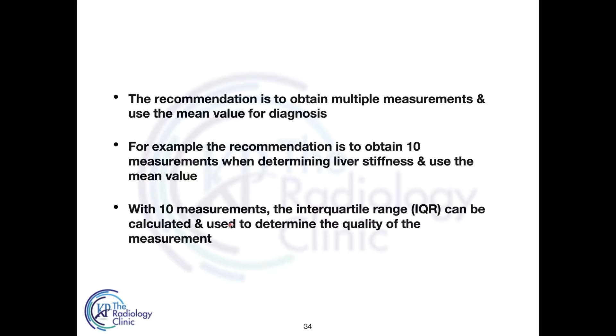With 10 measurements, we can get the interquartile range also, the IQR, and this can be used to determine the quality of the measurements. In 2D shear wave elastography, on the image to be used for measurements, one or more than one ROIs can be placed to obtain the stiffness values. Most systems allow for ROI size to be changed as desired. The color-coded image shows determination of stiffness values over a larger area. The area of maximum stiffness and the stiffness heterogeneity can be quickly identified.